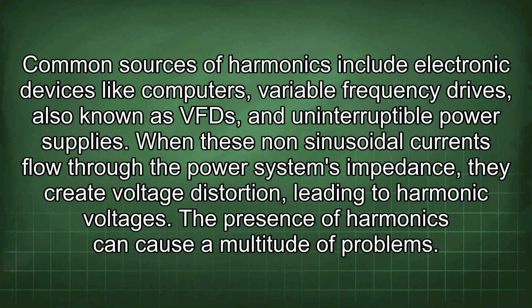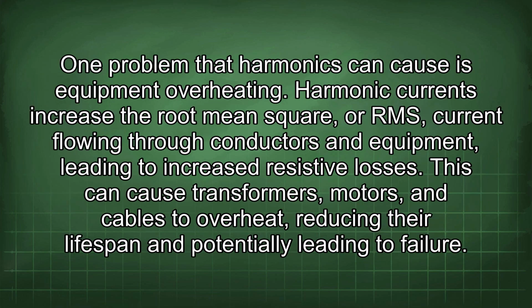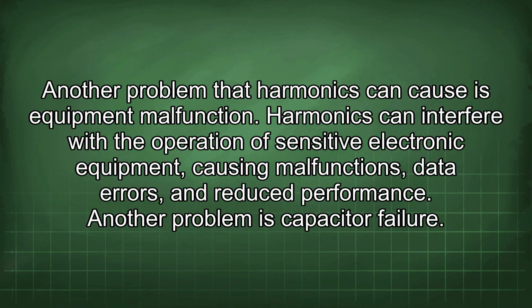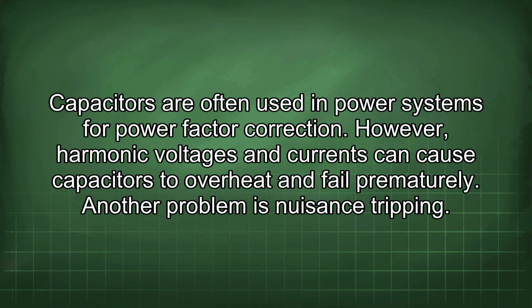The presence of harmonics can cause a multitude of problems. One problem that harmonics can cause is equipment overheating. Harmonic currents increase the root mean square, or RMS, current flowing through conductors and equipment, leading to increased resistive losses. This can cause transformers, motors, and cables to overheat, reducing their lifespan and potentially leading to failure. Another problem that harmonics can cause is equipment malfunction. Harmonics can interfere with the operation of sensitive electronic equipment, causing malfunctions, data errors, and reduced performance. Another problem is capacitor failure. Capacitors are often used in power systems for power factor correction. However, harmonic voltages and currents can cause capacitors to overheat and fail prematurely.